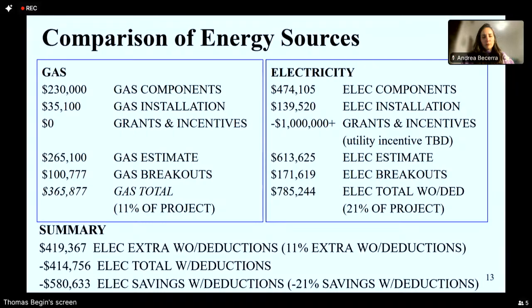This costs $420,000 more for heat pumps. But note, as stated earlier in this presentation, that the heat pump installation actually provides a higher level of redundancy in the heat - we can lose a whole unit and still heat the building. With the deduction for the $1 million incentive, that reverses and it saves $580,000 or so. And to reiterate what Tom said, the utility incentives are not included here. They're probably going to be six figures, but they're not nailed down yet.